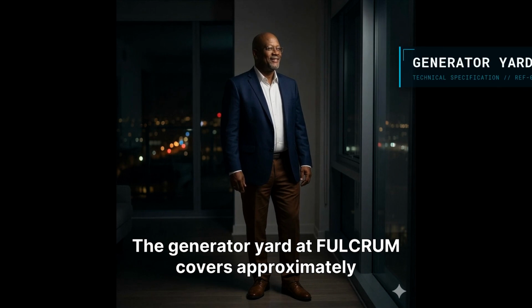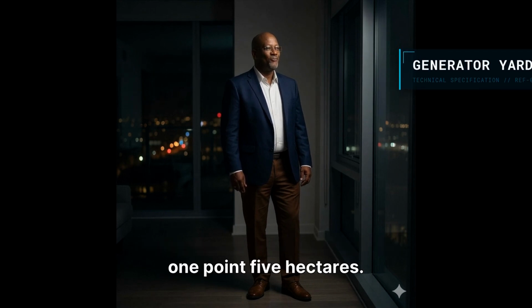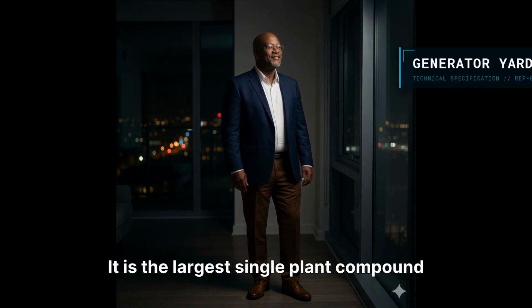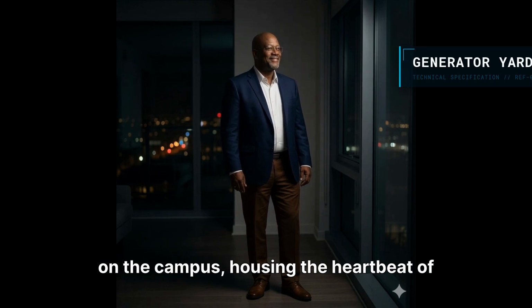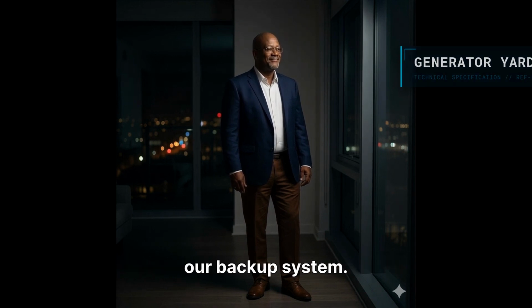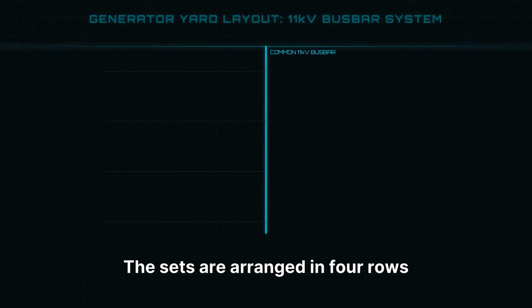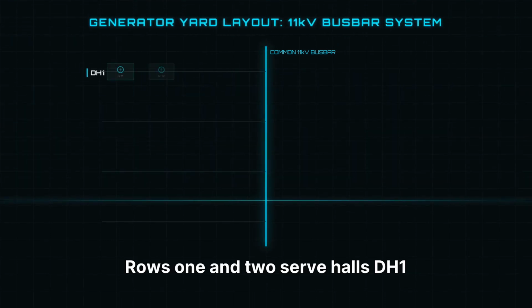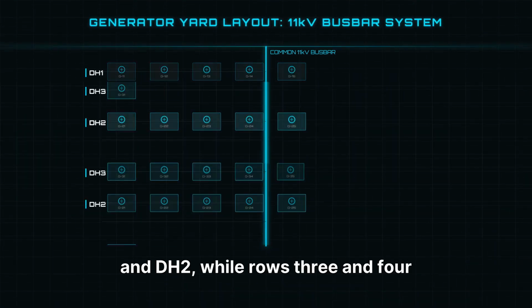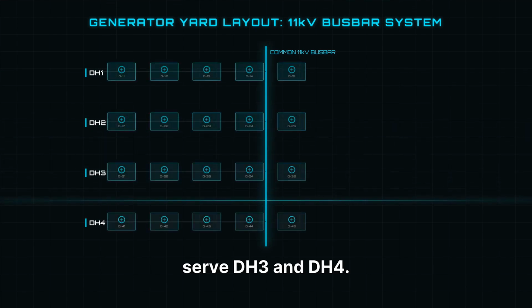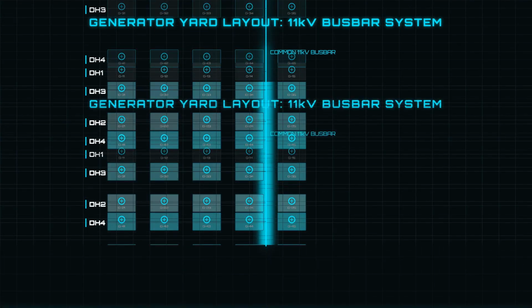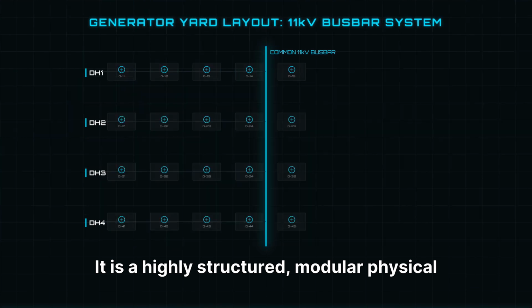The generator yard at FULCRUM covers approximately 1.5 hectares. It is the largest single plant compound on the campus, housing the heartbeat of our backup system. The sets are arranged in 4 rows of 5. Rows 1 and 2 serve halls DH1 and DH2, while rows 3 and 4 serve DH3 and DH4. It is a highly structured modular physical arrangement.